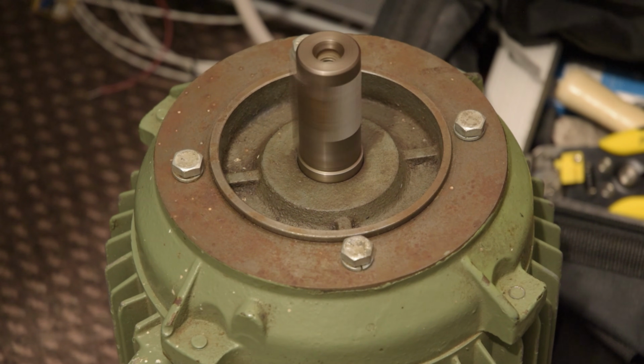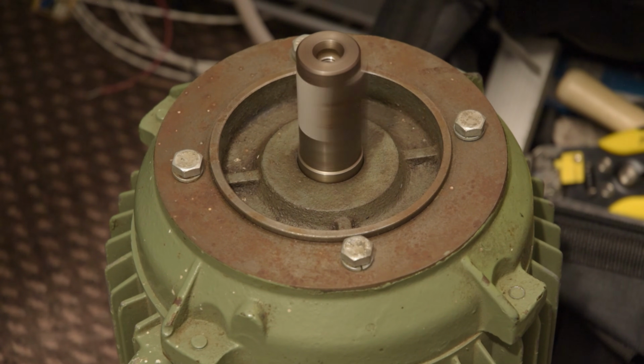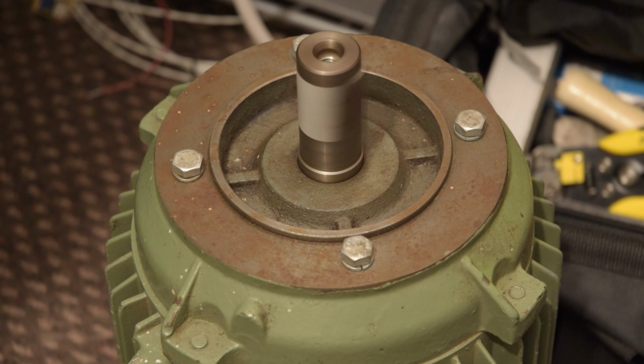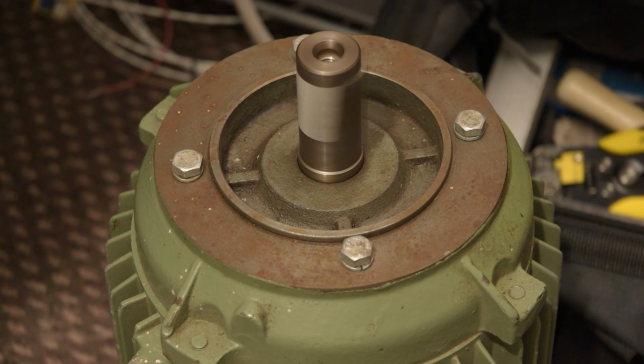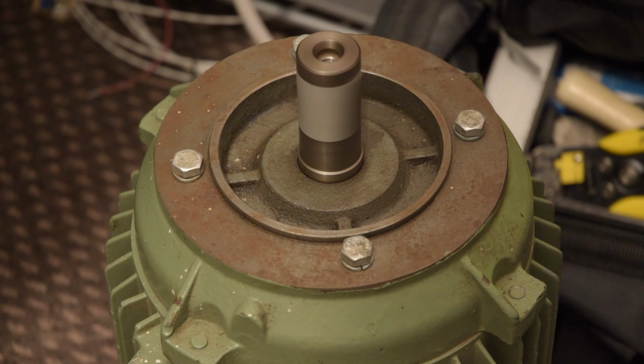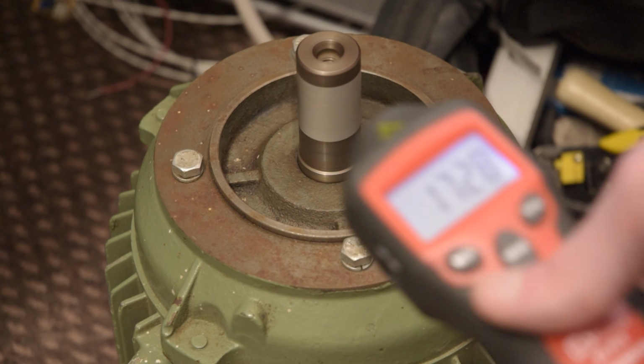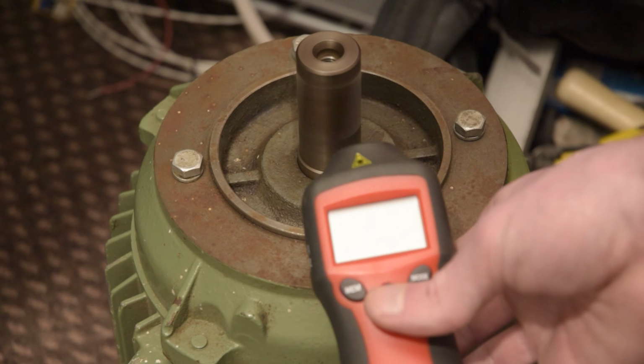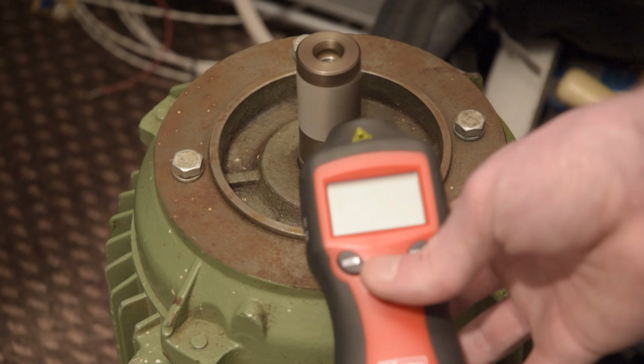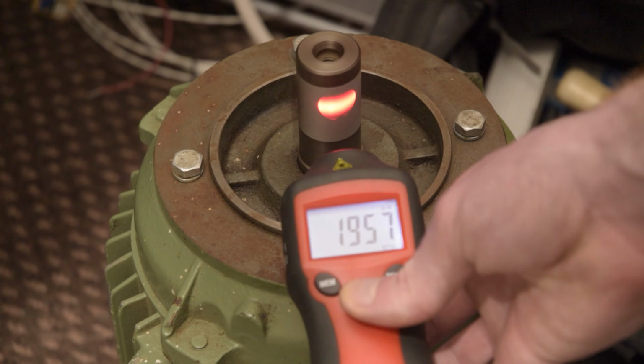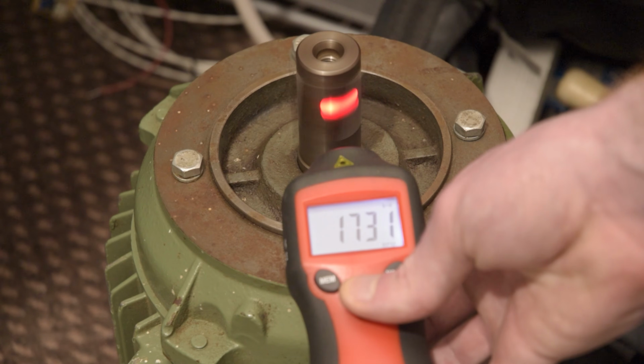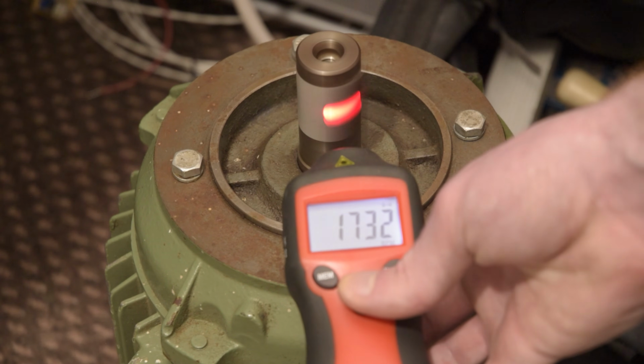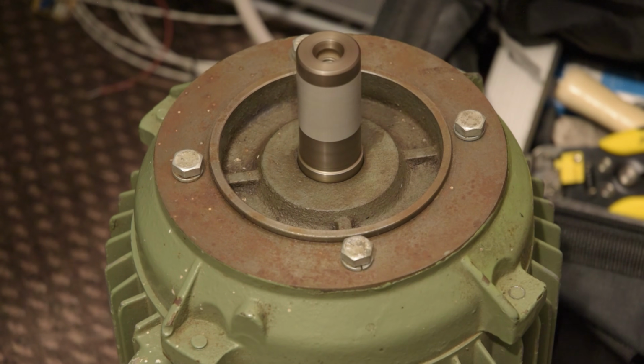It's rated for around 1500 RPM, and if I get the speed setting just right, I can get it to do about 1700, which I'll demonstrate now. This is what the white tape's for - this is my tachometer, hopefully you'll be able to see the screen. Let's have a go. Yeah, you can see that - just over 1700 RPM on a motor only rated for 1500.